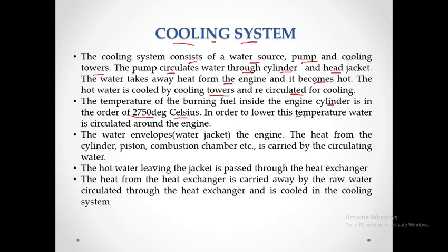So in order to lower the temperature, water is circulated around the engine. The water envelope, that is the water jacket, is used. The heat from the cylinder, piston, combustion chamber, etc. is carried by the circulating water. The hot water leaving the jacket is passed through the heat exchanger. Then the heat from the heat exchanger is carried away by the raw water circulated through the heat exchanger and is cooled in the cooling system.